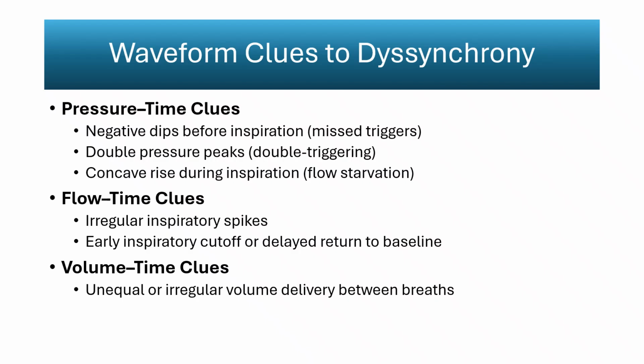On the flow time waveform, irregular inspiratory spikes represent abrupt changes in flow caused by patient effort competing with ventilator-delivered flow. These spikes disrupt the smooth inspiratory contour and signal that the infant is intermittently taking control of the breath. Early inspiratory cutoff, where flow suddenly drops before the infant has completed inhalation, suggests premature cycling. A delayed return to baseline reflects insufficient expiratory time or dynamic hyperinflation.